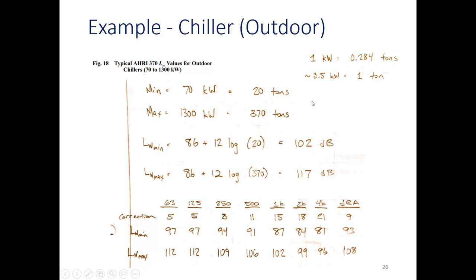Something that you will see: tons is a really common one, and then also seeing it in BTUs is really common in the US. The conversion factor for that is, I think, 12,000 BTUs equals 1 ton of cooling. So 60,000 BTUs would be a 5 ton unit. A lot of times you'll know it's a 5 ton unit, but the model number will have a 60 in it. So that's another conversion you should be aware of.